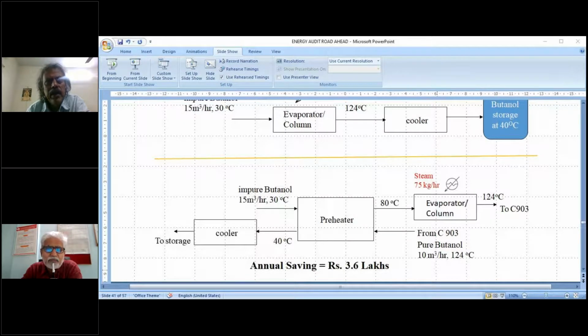The second thing is, if you look deeply into the process, perhaps there are some areas where this condensate water could be used. For example, in a pulping section, they may be using cold water, DM water, and then finally steam for heating the pulp. Instead, can you use this condensate or hot water for pulping?